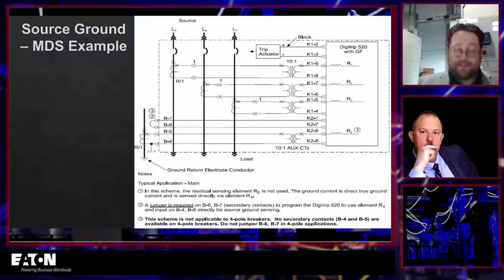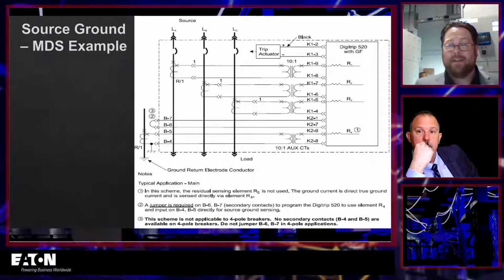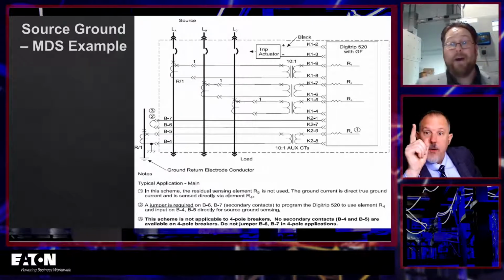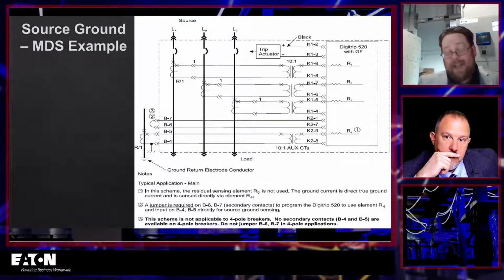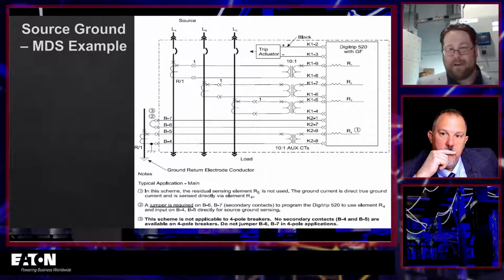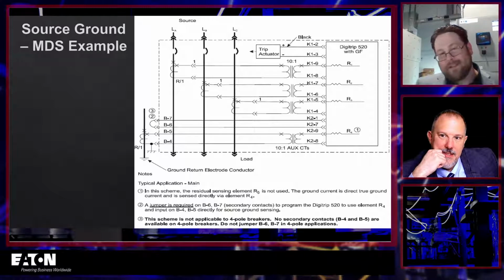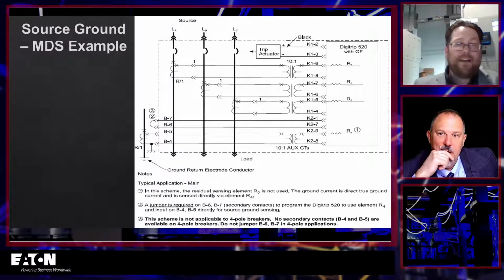It's interesting, we actually have a relay testing class in Warrendale happening this week. Oh, wow. It's awesome to have some in-person training taking place back here in the facility, an internal class. Ultimately, they're testing relays, and they were trying to test zone selective interlocking. I just happened to walk in the room. They said, Mike, this isn't working. We know that you're a smart guy. Can you help us out? I was dumbfounded. I couldn't figure out what they were doing wrong. Then one gentleman turned the relay around and looked at the screws. He said, oh, there's actually a jumper right here. I didn't even see it because it's a small little jumper. So they're very easy to miss.